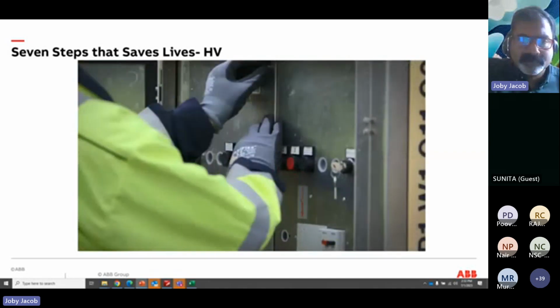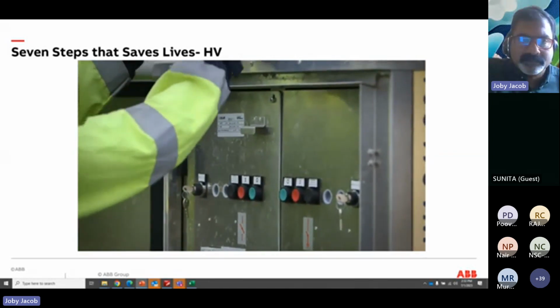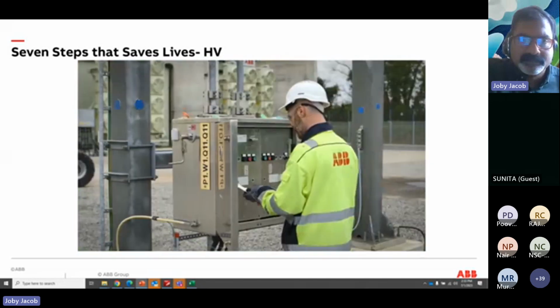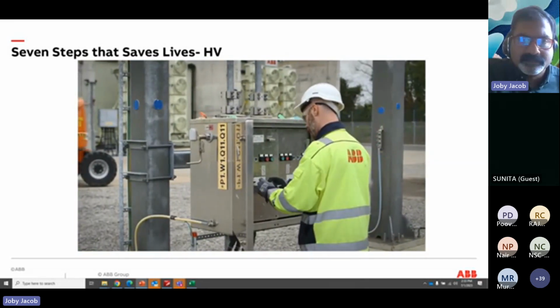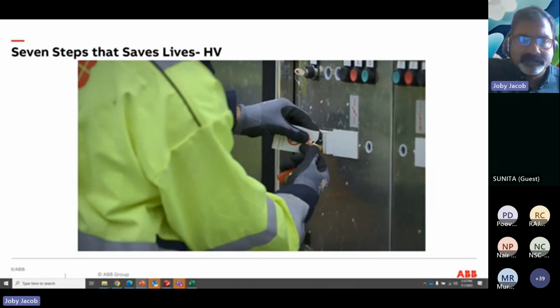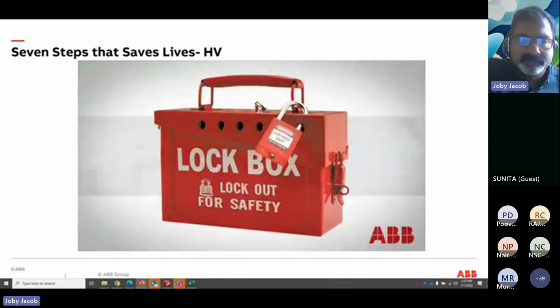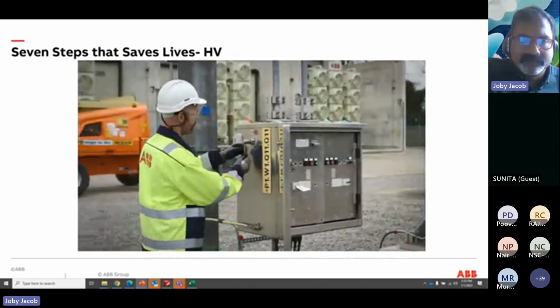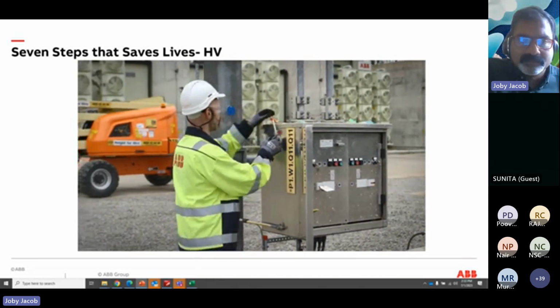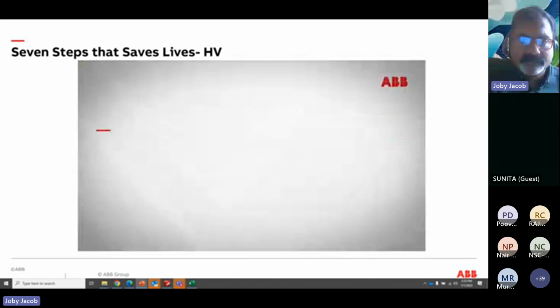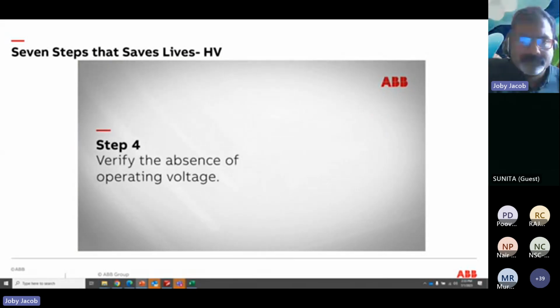Secure against reconnection by applying lockout-tagout, and if possible, avoid allowing other work to take place at the points of isolation. If there are multiple points of isolation, group lockout-tagout shall be implemented with the person in charge of work, or PICW, acting as the group lockout-tagout leader. Step 4. Verify the absence of operating voltage.